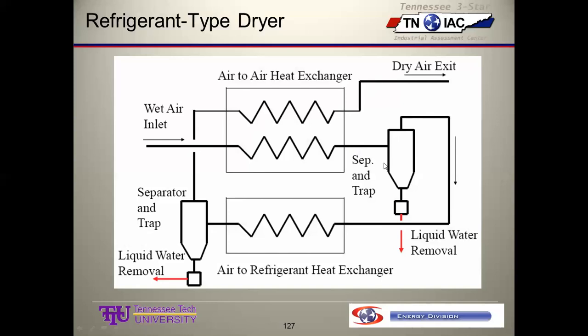We show a separator and trap on both sides. It depends on the manufacturer. Some, you have to have this one for sure. Some manufacturers may or may not have this. They may want you to spec it upstream, whatever. So this air has been pre-cooled, but it's still pretty warm, and it's got a lot of water vapor. It's essentially saturated when it comes in, so the relative humidity is 100% on this side. When we start cooling it down, we're going to get some moisture out of this. That's the point of having a moisture separator here. We'd like to go ahead and get that out if we've already condensed it. And then when it gets in here, it's still going to be saturated.